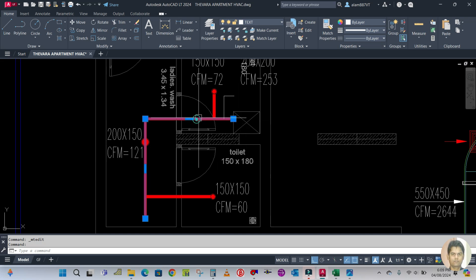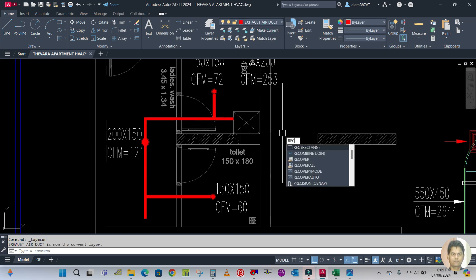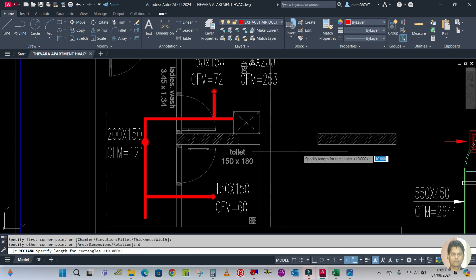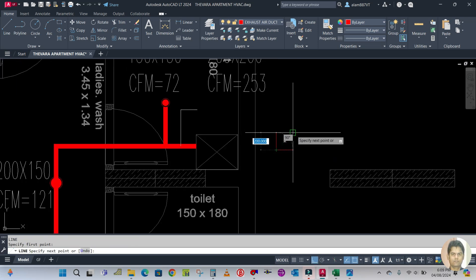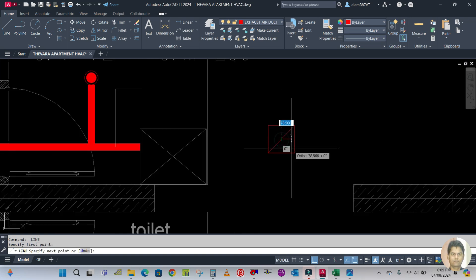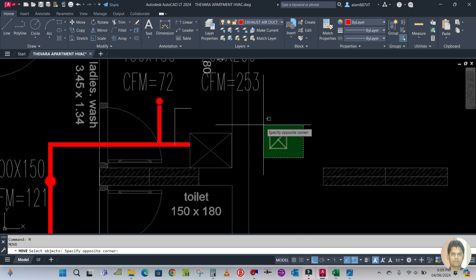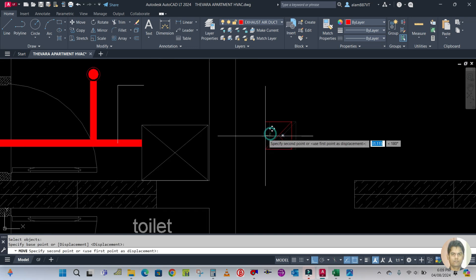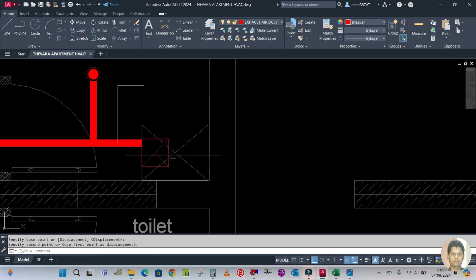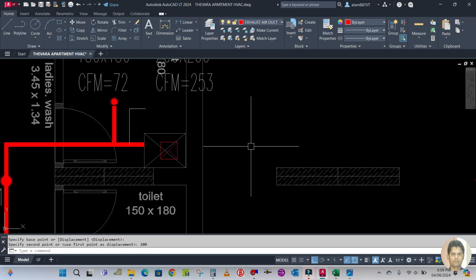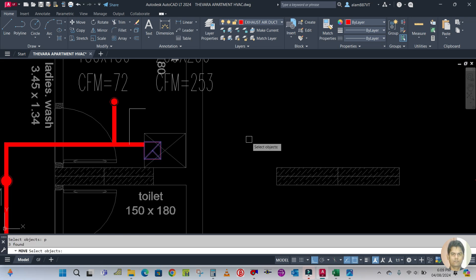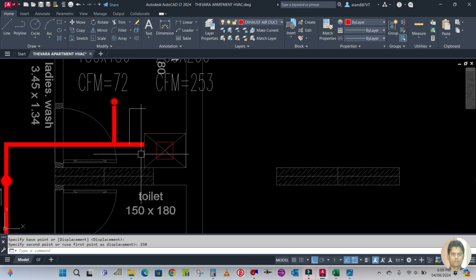The duct size is 200 by 200. Let us start by creating one riser — a rectangle equal to 200 by 200. This is your riser duct. For the exhaust duct, we are showing it like this — not like a return, this is an exhaust duct. Move this duct to the center of this riser using move command — M for move, P for previous. From the riser duct, keep a minimum of 150 to 200 mm clearance.